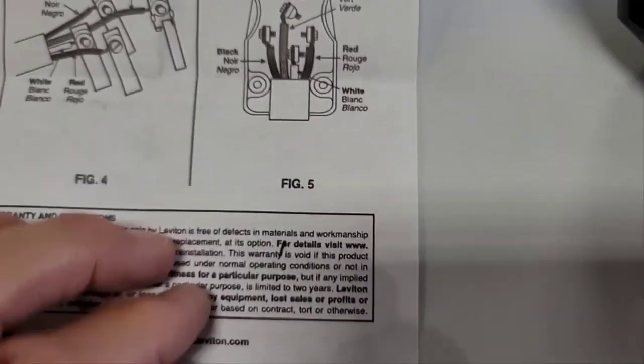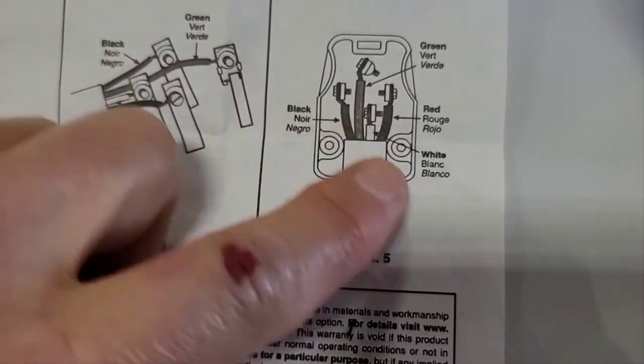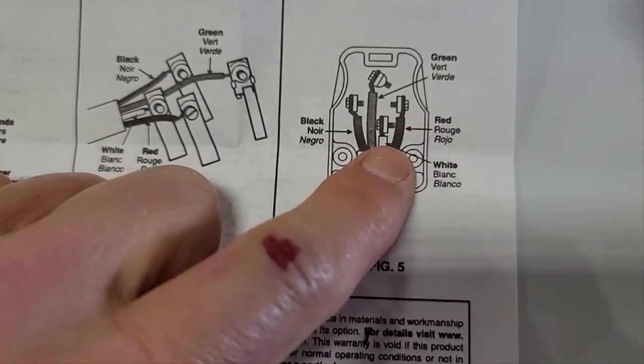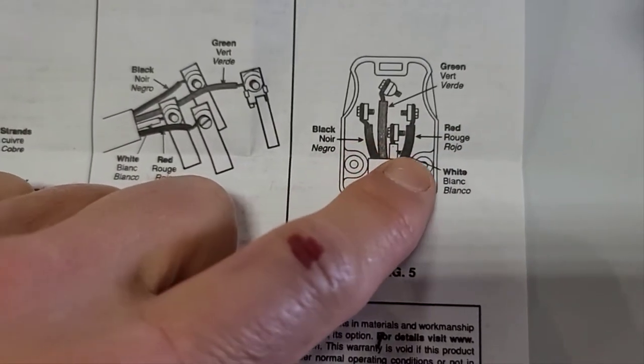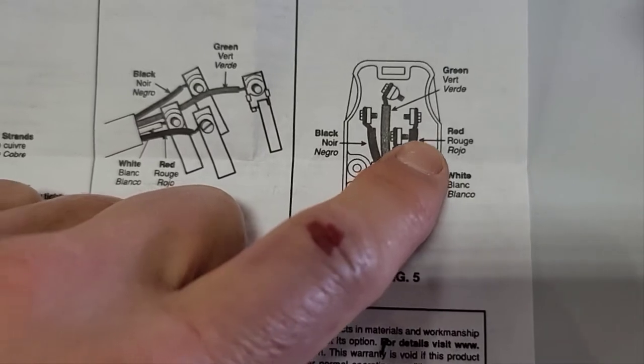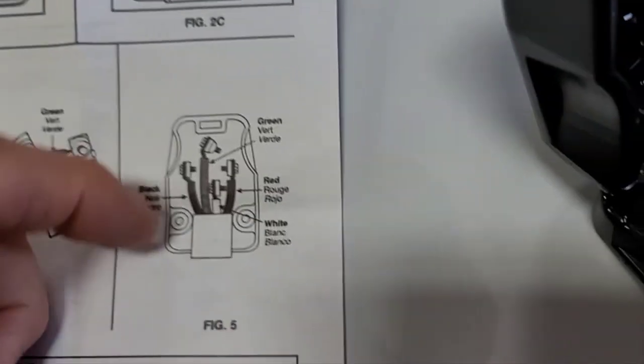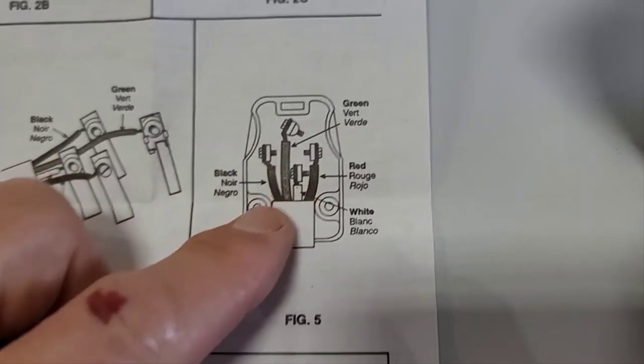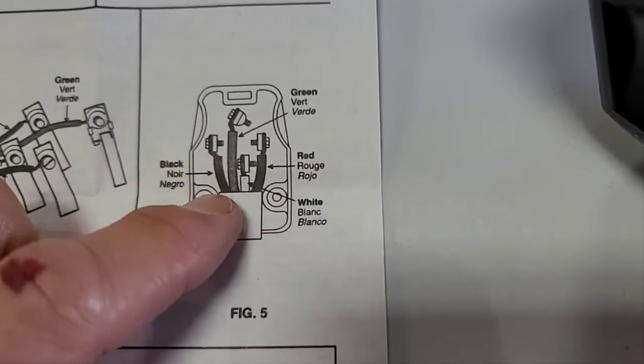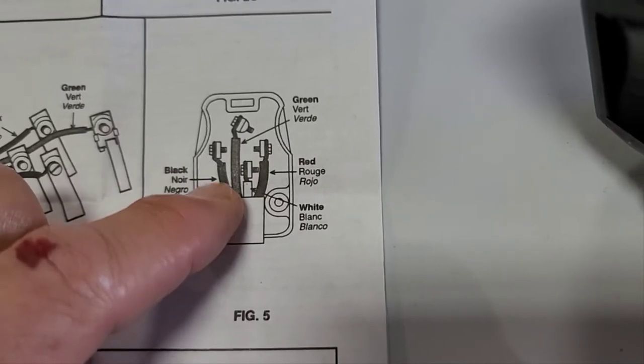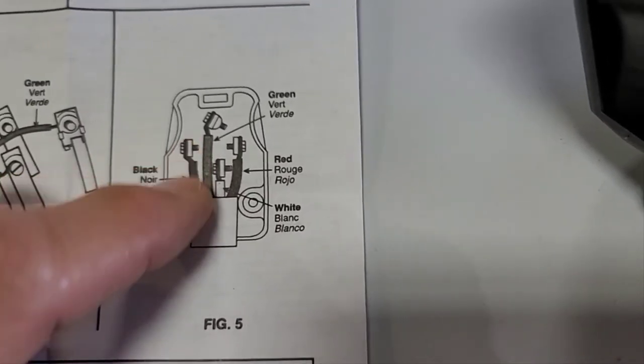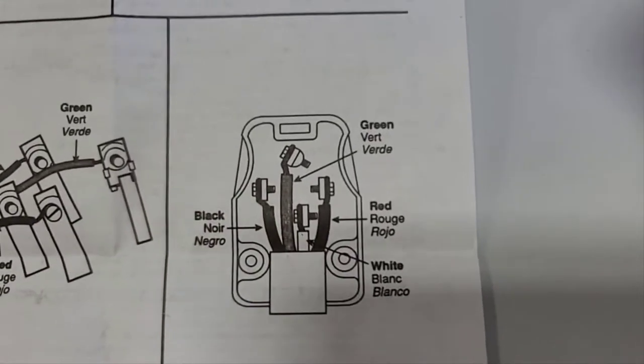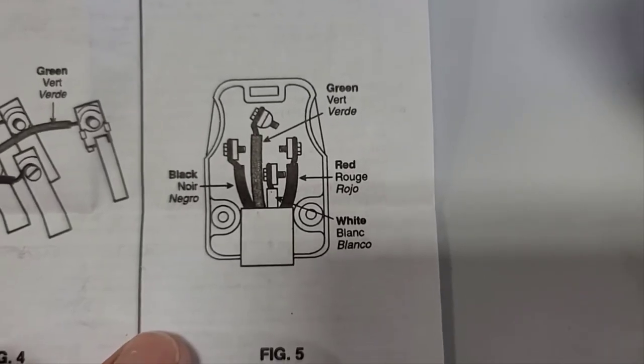And let you have a picture of the strip gauge. And then the way they routed this. Yesterday I routed the wire there, the hot wire there and the neutral, but I had the ground wire going in between the hot and the neutral to the right and I realized that was a bad choice because of the screw. So I pulled them all out and I routed it to make sure that it's hot and then your ground wire and then your neutral. So that's important. I'll pause on that for a second.